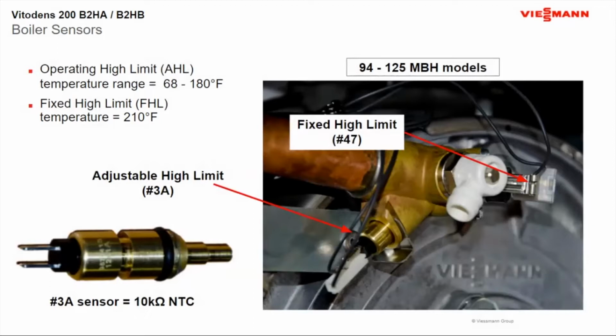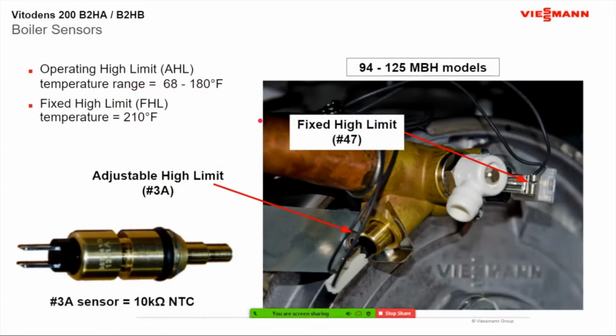Just showing you our sensors here, just to show you that they are all numbered as well. So all our plugs, all our sensors are all numbered to make it easier for troubleshooting as well as replacement. It also gives you the temperatures that they will operate to. So our adjustable high limit, which is going to be that number 3 sensor here, is a range from 68 to 180. And remember, if you're using your outdoor sensor, we have boiler protection. So cold weather protection. On this boiler here, as soon as it hits 32 degrees outside, it maintains 68 degrees on the boiler. Maximum temperature with our smaller 200s is 180 degrees. A fixed high limit goes off at 210.